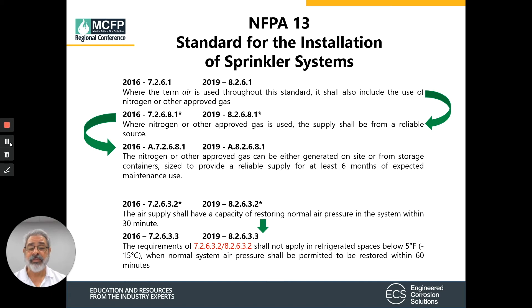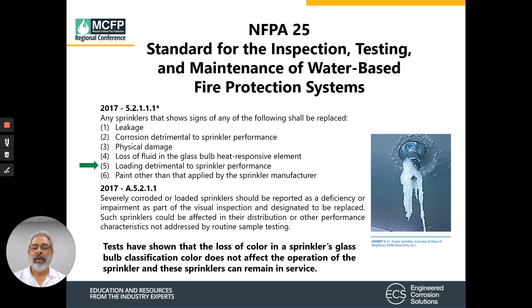When talking about the air supply and meeting the 30-minute fill requirement, when working with cold storage applications, that timeframe has been increased to 60 minutes instead of 30 minutes. So if your refrigerated space is below 5 degrees Fahrenheit, you're allowed to extend the fill time from 30 to 60 minutes. By slowing down the gas going into the sprinkler system and filling it slower, there's less potential for additional moisture or ice accumulation during the fill time.